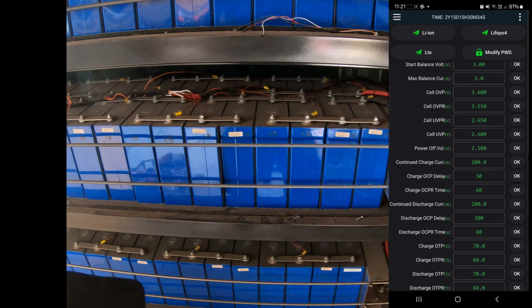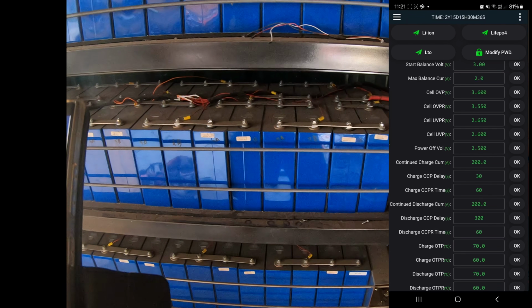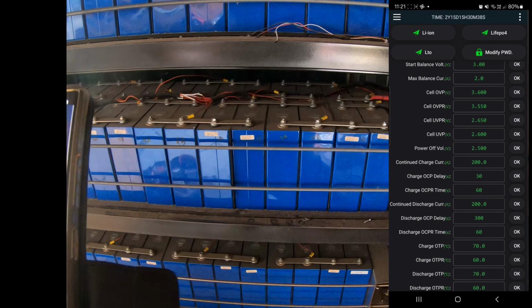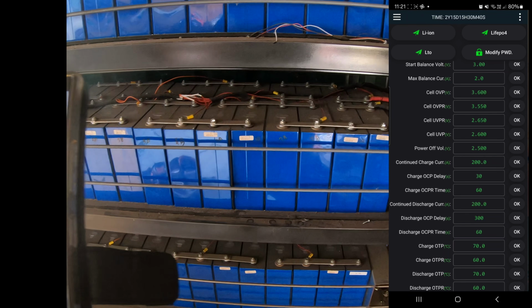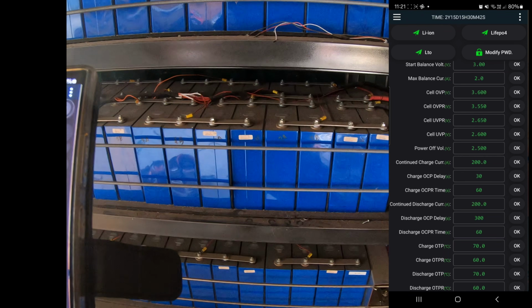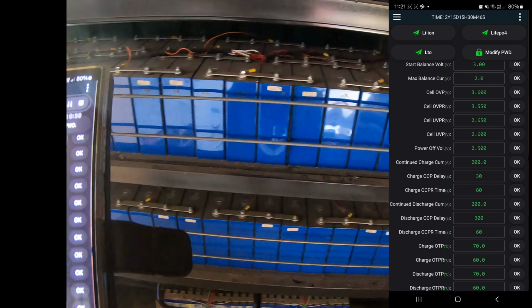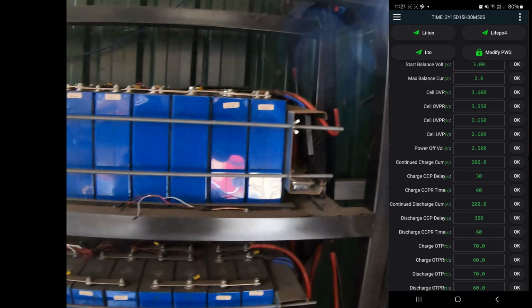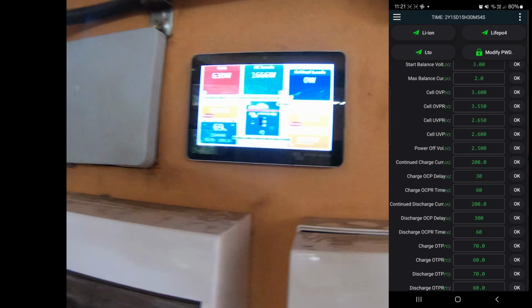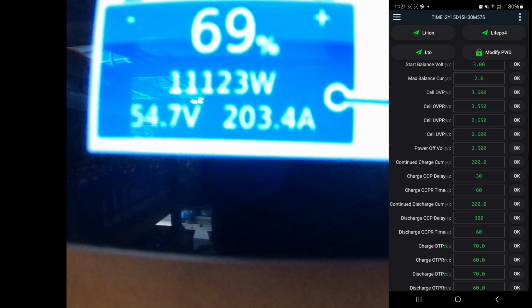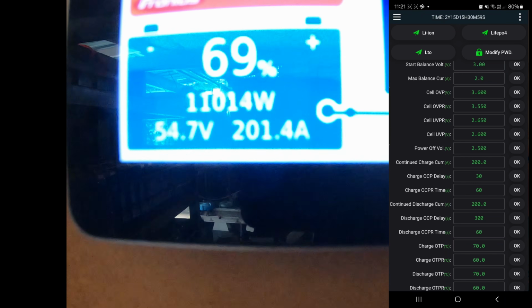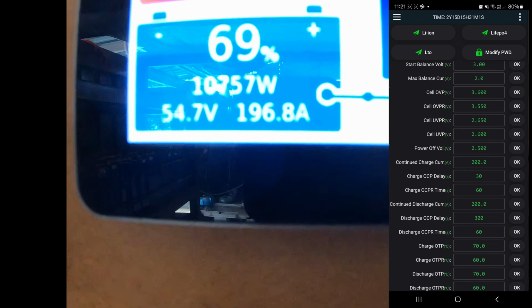I suppose you're really only ever going to hit that if you've left the pack sitting around for the longest time and it's discharged itself well under 2.60 on its own, or maybe you've got a faulty cell. Continuous charge current is 200 amps, so that's 200 amps per BMS, so we could potentially be charging this thing with 600 amps. It's a shame I wasn't recording that. It's getting 200 at the moment. Well, that's 200 across all three, right? We're not even touching the sides of this thing.